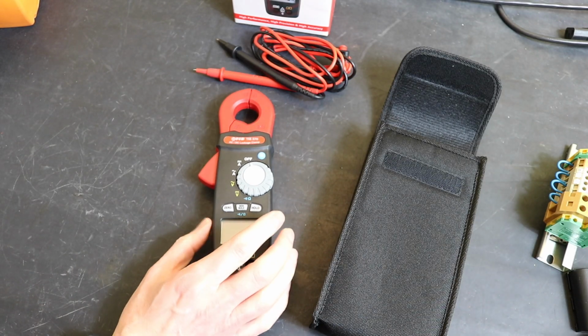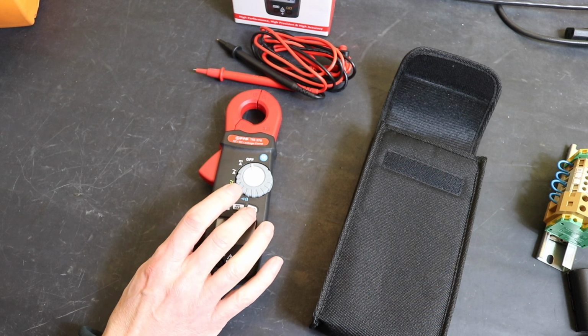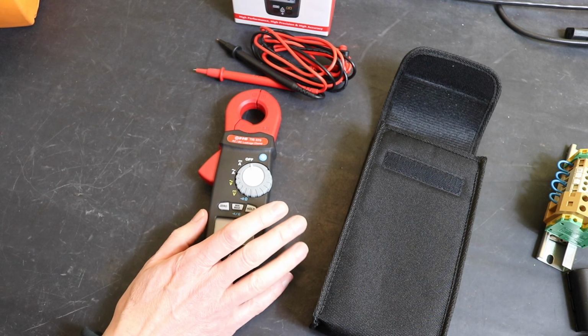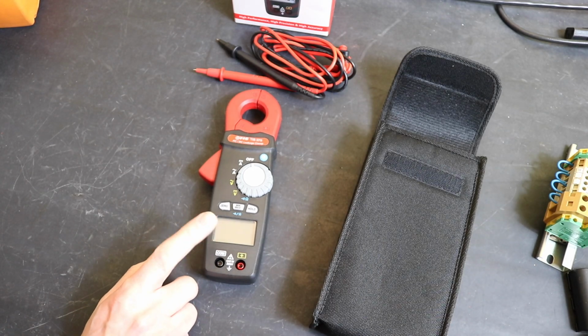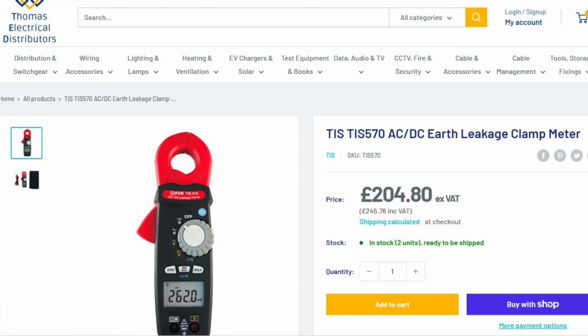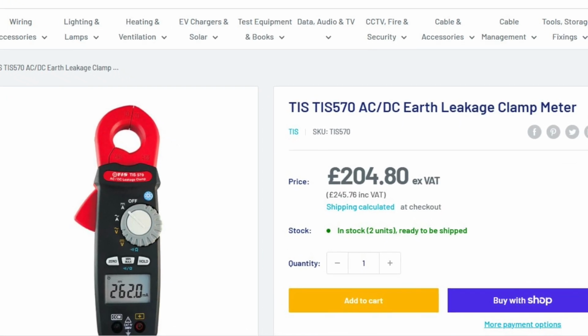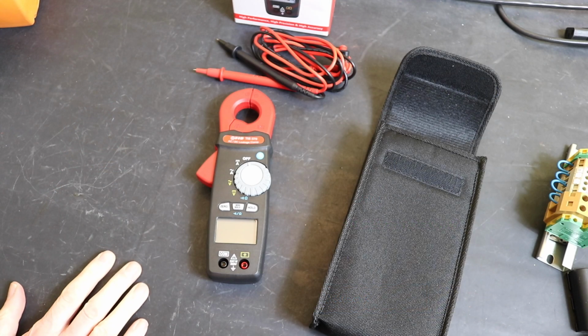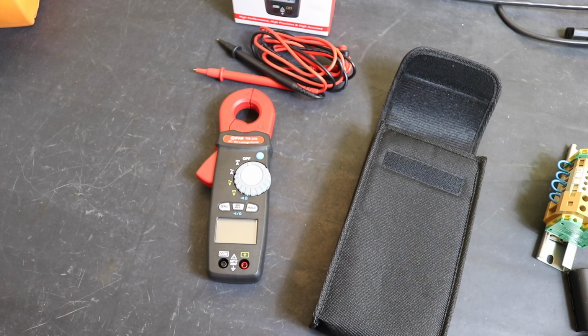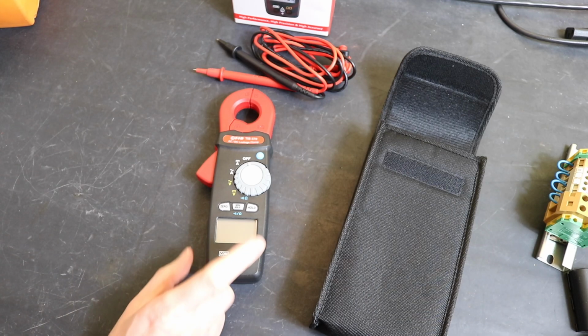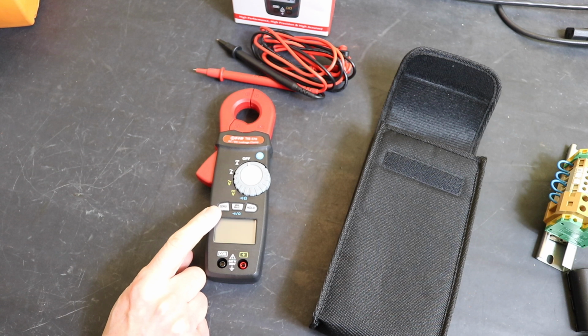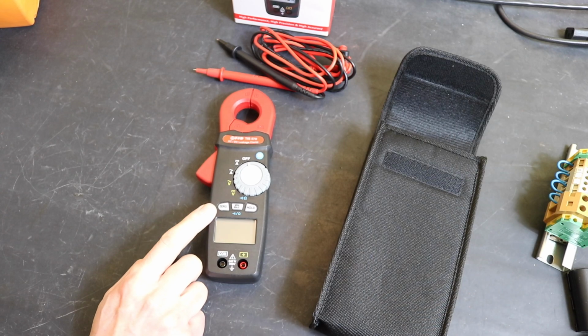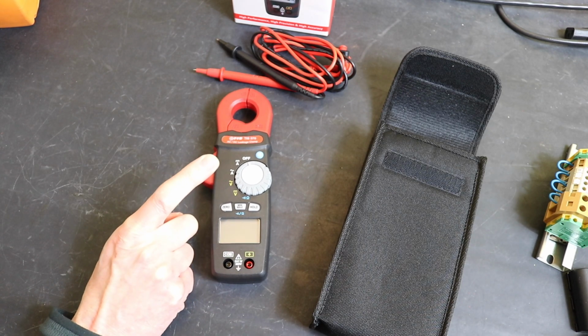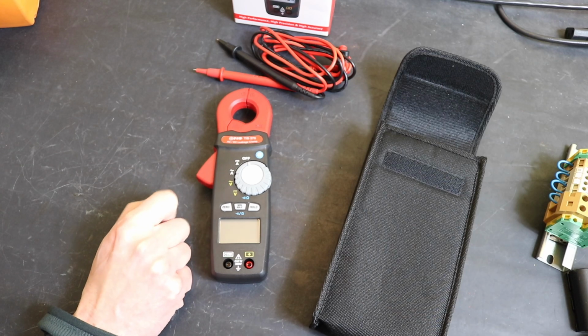In terms of price, this ranges from around £250 up to £300, and they're available from electrical distributors. CEF have a fair bit of TIS equipment in. I got this one from Thomas Electrical Distributors because it was slightly cheaper - I paid around £250 for this one. In terms of price against other clamps, that's similar to the Megger unit. The Metraclip is a bit cheaper, and these earth leakage clamps go from around £100 all the way up to £800 for a unit from Fluke, but the vast majority of them cannot read DC leakage current. This is one of the only ones that can, along with the Uni-T one.